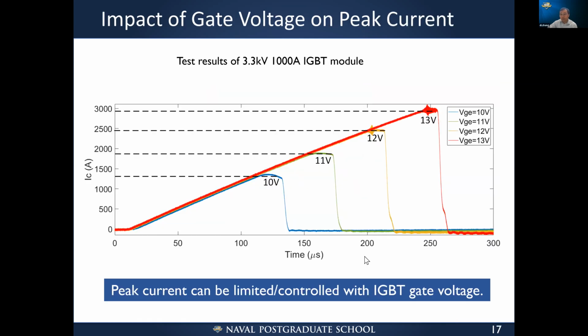This is an example showing test results for a 3.3 kilovolt, 1000 amp IGBT module. If you reduce the gate voltage from 15 volts to 13, 12, 11, 10, as you can see, the fault current, the current that can flow through the saturated IGBT, is limited by the IGBT, which means no matter how hard you try, the current flowing through the IGBT is limited. The terminal voltage across the IGBT will increase automatically to fight against it. So we pick 12 volts. The peak current is about 2.5 to 3 times the rated current. I think it is a reasonable value.